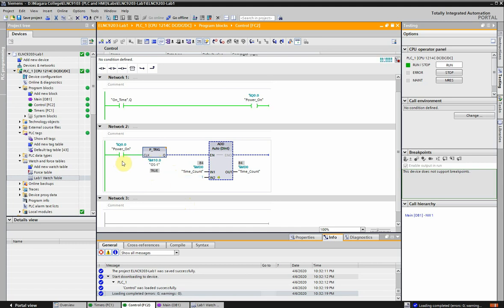off, which I couldn't see before when I was just using the normally open symbol with a P in it. When I was using the normally open symbol with a P in it, I could not actually see power on cycle on in this format. When I use P_TRIG, I can see the input turn on. Now typically you would use P_TRIG if you've got more than one condition on the input and you want to monitor a whole set of statuses as a result of logic operation on the input, but it also comes in handy just for the single bit that you're monitoring because you can watch that bit cycle. So it's kind of handy that way.